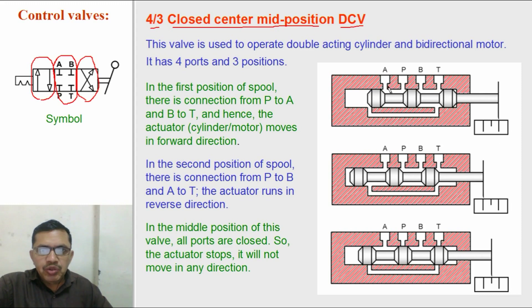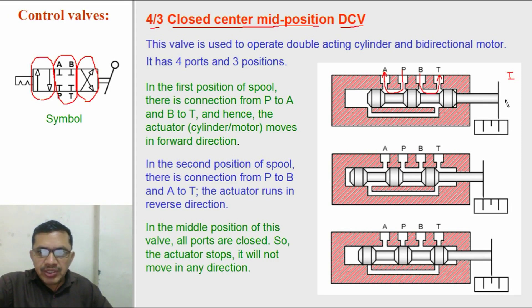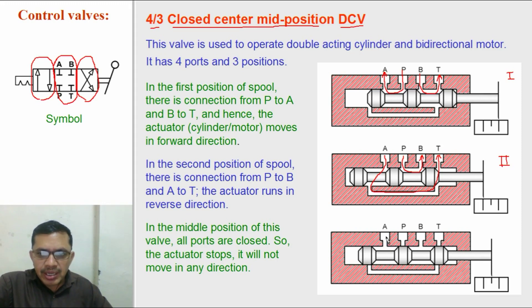This is the construction of the four by three closed center mid position direction control valve. In the first position there is connection from the pump port to cylinder port A, and from cylinder port B to tank port T. When we shift the lever of this valve, the spool will be shifted to the second position. In this second position there is connection from the pump port to cylinder port B, and from cylinder port A oil flows through the valve to tank port T.